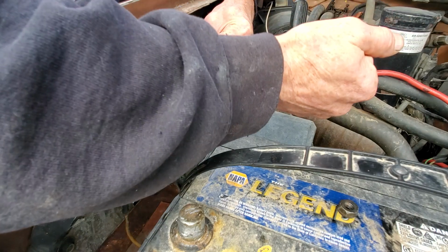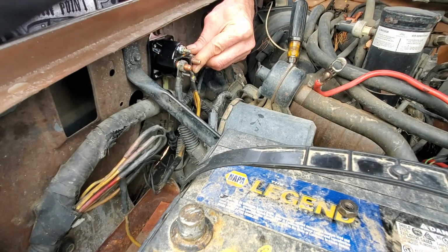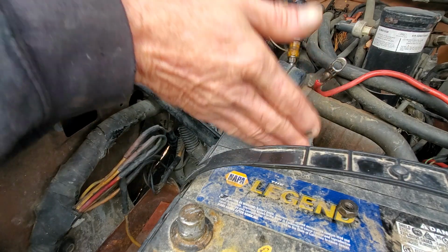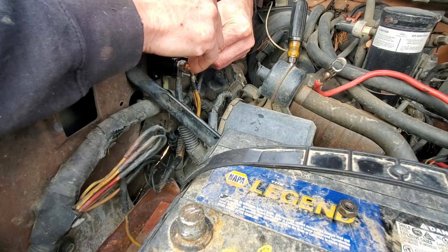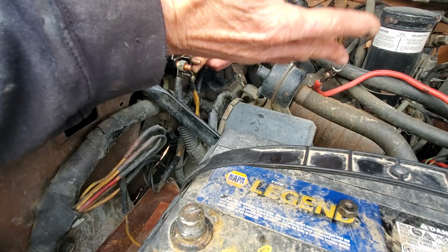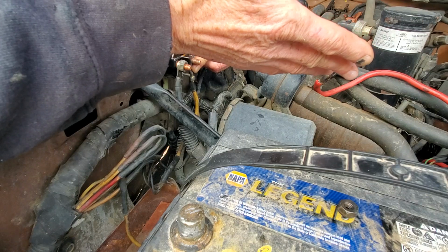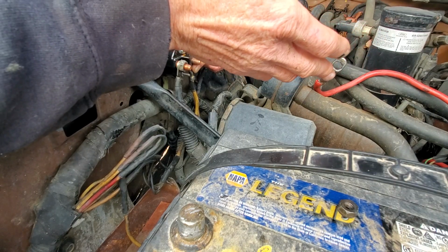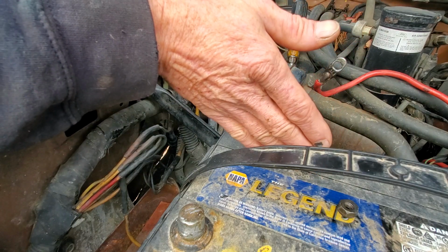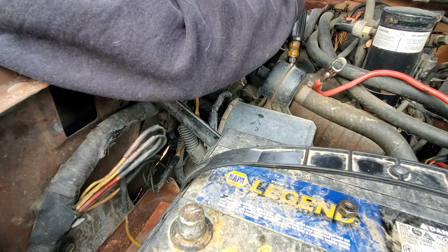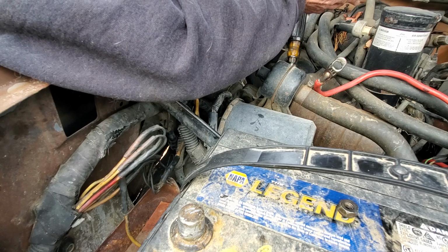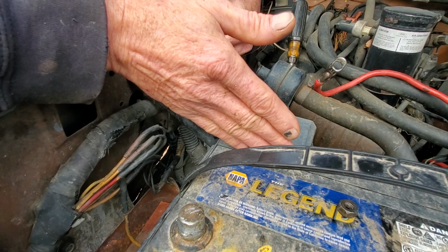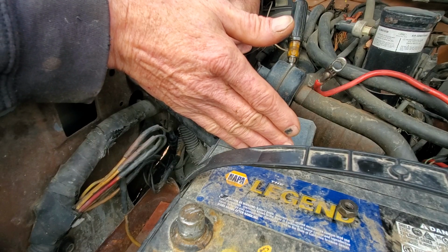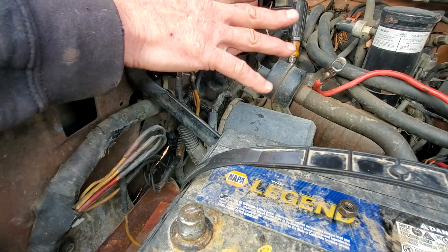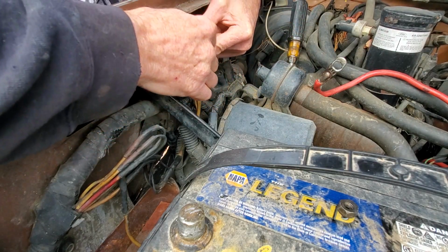So when you have scenarios you can't control, like the alternator not always putting out the same amount of current to recharge the battery or to run the car — because there are conditions where you have a dead battery, and under normal conditions that alternator only needs to supply 20 amps even though it's a 150 amp alternator. You could have a dead battery, get a jump start, and now your alternator is not only supplying you with 20, 30, or 40 amps to run the car, but it's also sending out about 50 amps to recharge the battery. That's all strain on the fuse links.